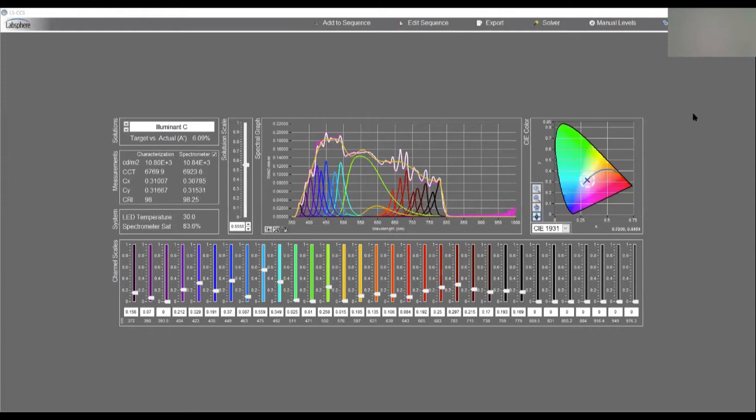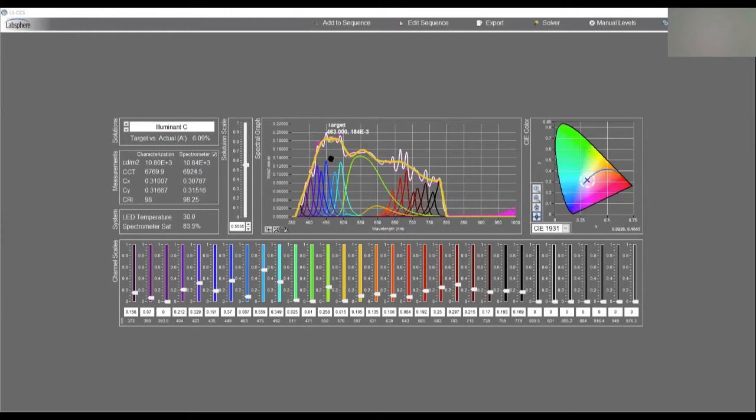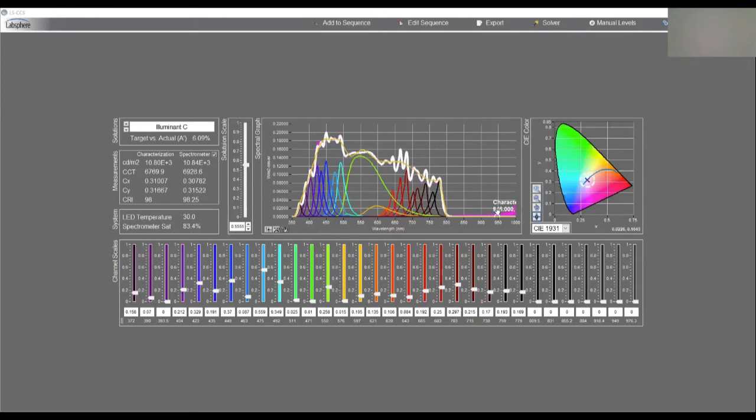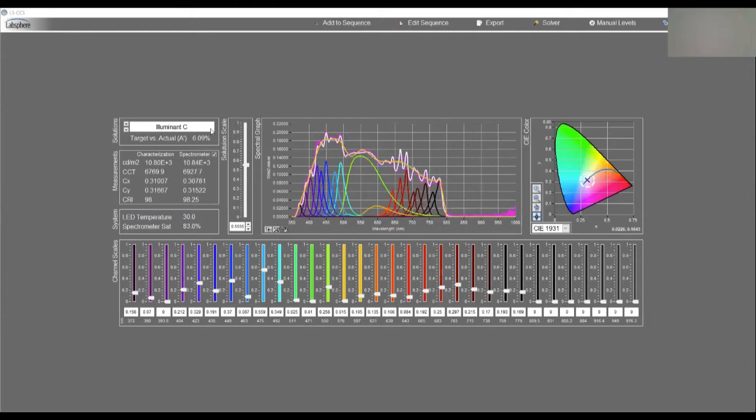Just to re-familiarize yourself with our system, the gold line is the target spectrum. The white line is how well it's matching. That's the optimization file which we're going to show you how to produce. The pink line is a measurement done by a spectroradiometer inside the system. So this is the spectral radiance output of the system and that is showing you the output here on the left.